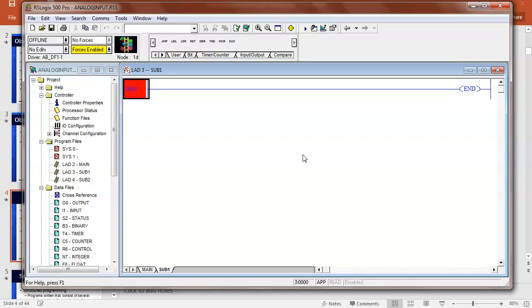You can repeat rungs, by the way. Some of y'all have gotten problems with that. The problem is if you use an output another time, you don't get an error when you check your compile, because everything's in the right syntax, right? But what's been happening is some of y'all have duplicated outputs. Well, if one output says it's off and the other output says it's on, then it just stays off, right? But what you can do is duplicate a rung and use the same output.